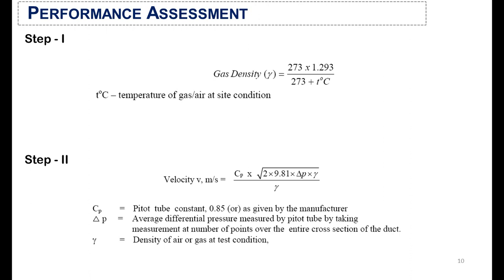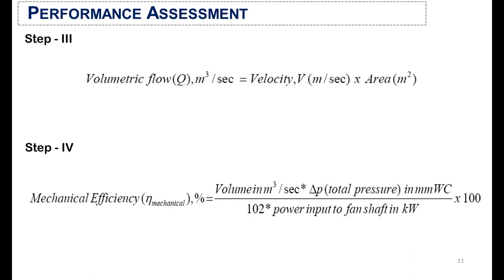In the first step of performance assessment, you need to calculate the gas density. Here is the formula to calculate the gas density, where T is the temperature of the gas at site conditions. Once you have calculated the gas density, you use this value for the calculation of velocity in step two. In step three, calculate the volumetric flow rate of the gas. Finally, in step four, calculate the efficiency of the fan or blower using the pre-calculated values.